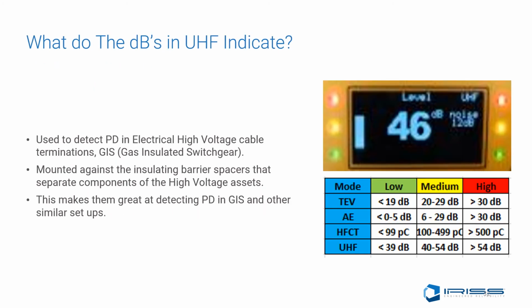So what do the decibel values in UHF indicate? Well, if we use them to detect partial discharge in electrical high voltage cable terminations, better known as GIS or gas insulated switchgear, we would mount the UHF sensor against the insulating barrier spacers that separate the components of the high voltage assets. This makes them great at detecting the PD inside of the GIS and other similar setups. A low alarm would be considered anything below 39 decibels. A medium alarm value would be 40 to 54 decibels. And a high alarm value would be 54 decibels and higher.